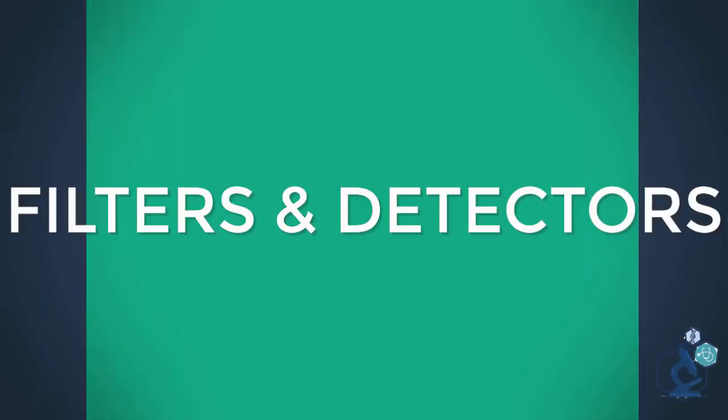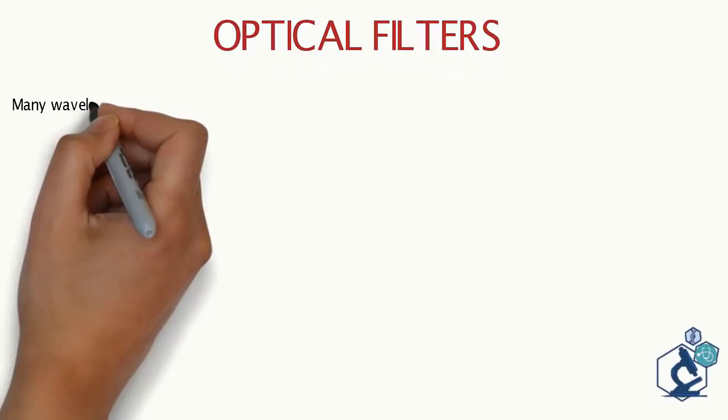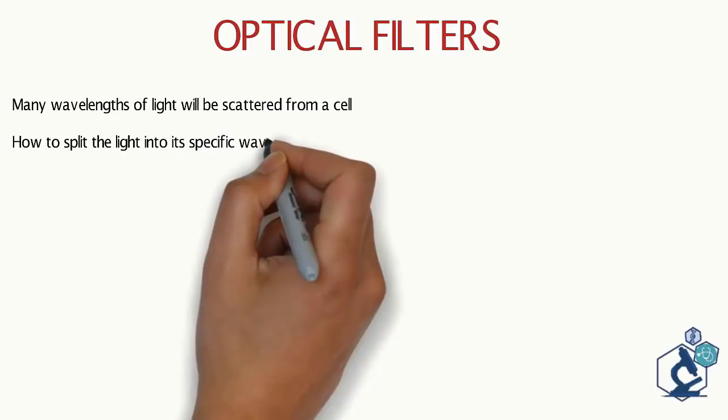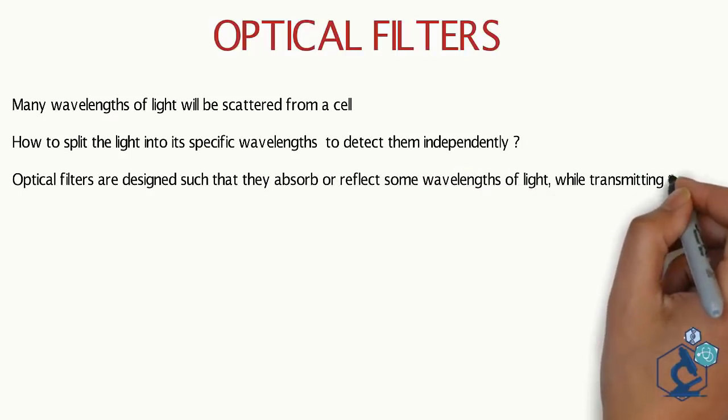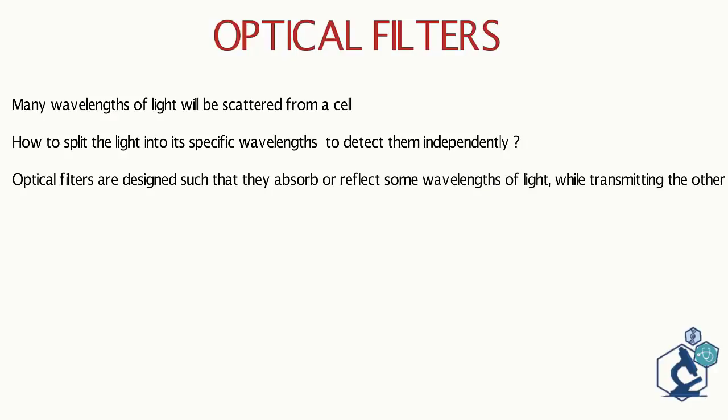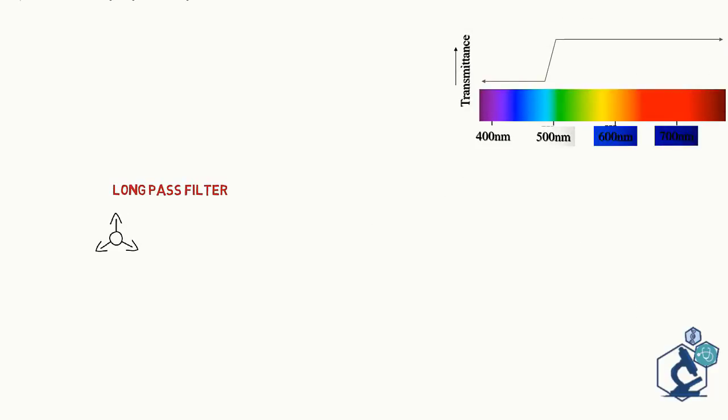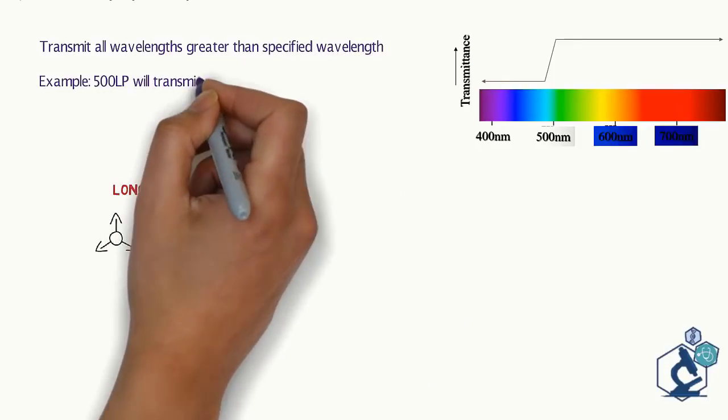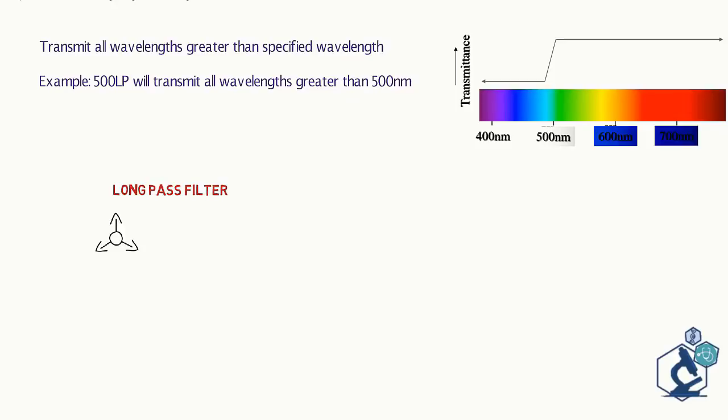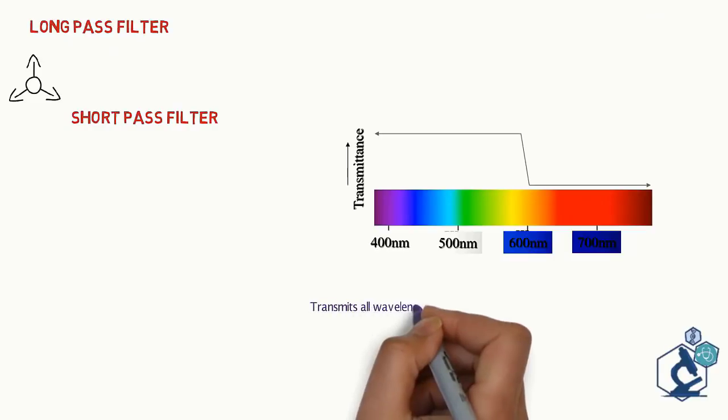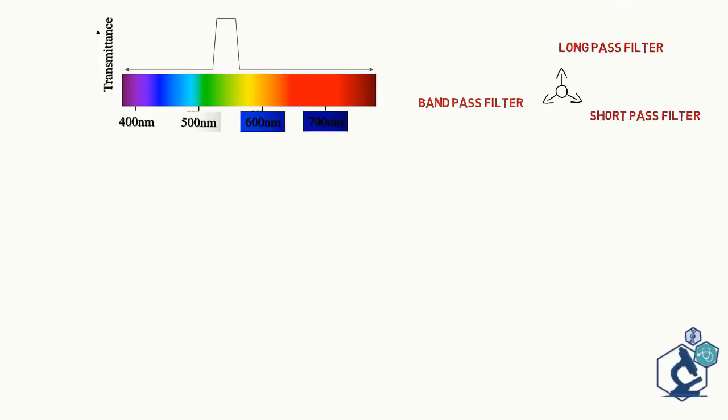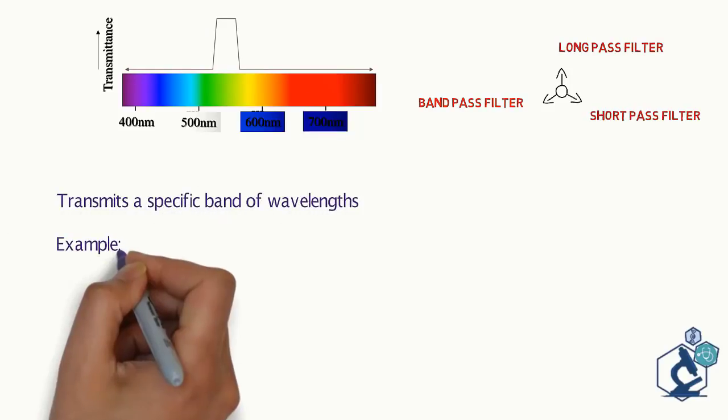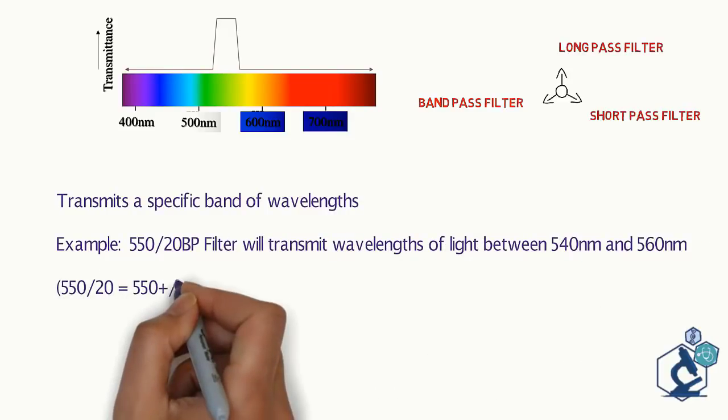Now coming to filters. Many wavelengths of light will be scattered from a cell. We need a way to split these lights into its specific wavelength in order to detect them independently. This is done with the help of filters. Optical filters are designed such that they absorb or reflect some wavelength of light while transmitting the other. Three types of filters are generally used: long pass filter, short pass filter, and band pass filter. Long pass filters transmit all wavelengths greater than the specified wavelength, e.g. 500 LP will transmit all wavelengths greater than 500 nm. A band pass filter transmits a specific band of wavelength, e.g. 550/20 BP filter will transmit wavelengths of light between 540 nm and 560 nm.